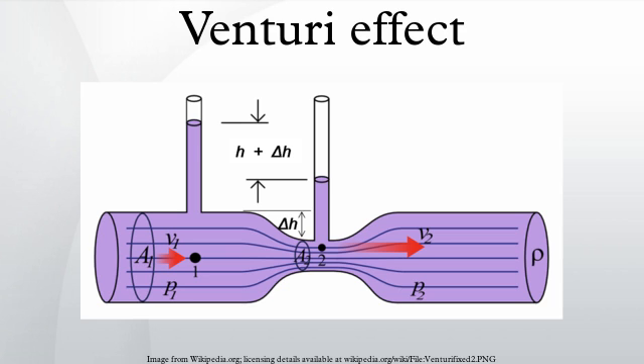When a fluid such as water flows through a tube that narrows to a smaller diameter, the partial restriction causes a higher pressure at the inlet than at the narrow end. This pressure difference causes the fluid to accelerate toward the low pressure narrow section, in which it thus maintains a higher speed. The Venturi meter uses the direct relationship between pressure difference and fluid speeds to determine the volumetric flow rate.